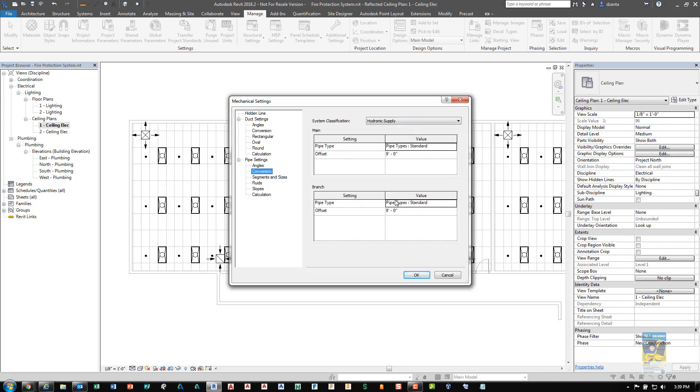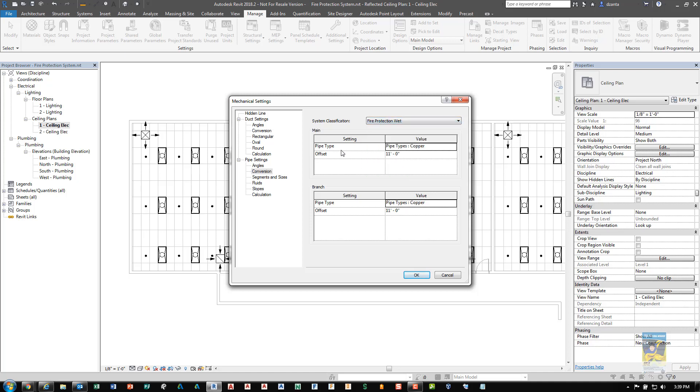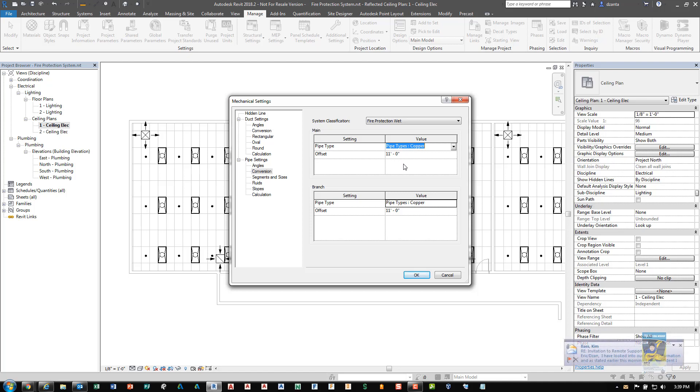You have different conversion capability. So for us, we want to take a look at the system classification that's going to be fire protection. We can choose any one of the four that they give us. So for example, if I choose wet, I can go into the main setting and specify whatever type that I want. And I'll leave it as copper and I'll set it as 11 feet high. The reason I did this is because the standard default project is 10 feet high. The standard ceiling is 8 feet high. So from level one to level two is 10. So I figure I just place it at that high. It's easier to see in the view.